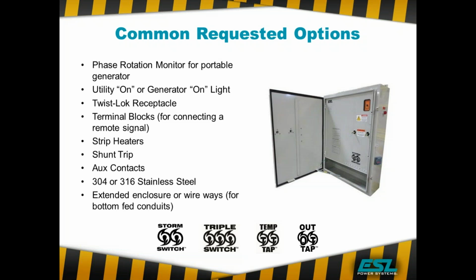You have the phase rotation monitor. So when you hook up a portable generator, you know that it's in the same phase as your utility or your permanent generator. We have the utility indicator lights off there to the side, the little red light, so you can tell when either the utility power has been restored or the generator is on.